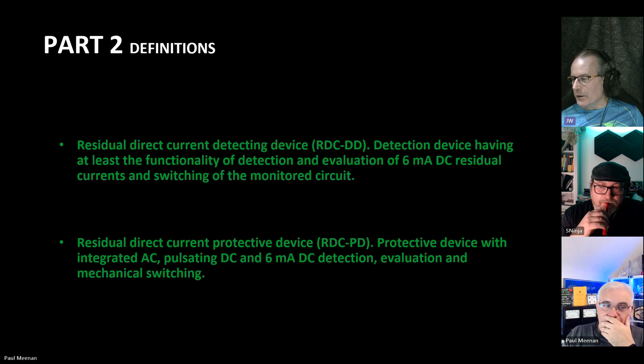I'll be honest with you, I've researched the arse out of this, RDC-PD. The difference is that one of them is going to detect it but not necessarily cut off the supply - it might just signal an alarm for someone else to act on. The PD version is the actual device that, if it detects this, will disconnect your circuit, in most cases aimed at electric vehicle charging. Well, there's also a definition for secondary battery: an assembly of secondary cells for use as a source of energy.